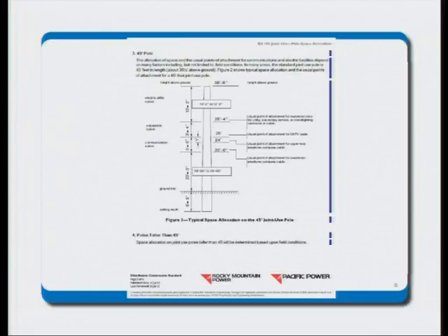That keeps all the conductors up high enough so that they don't get snagged by trucks or cars or anything else. And then you have several feet of space allocated for what we call the communications space. So you're going to have multiple opportunities for attachments in that space. And then you need to have this safety zone. It's called the communications worker safety zone. It varies by the voltage that's above, but the typical space for a communications worker safety zone is 40 inches. So between the top communications attachment and the lowest power attachment, you have to have this free zone.